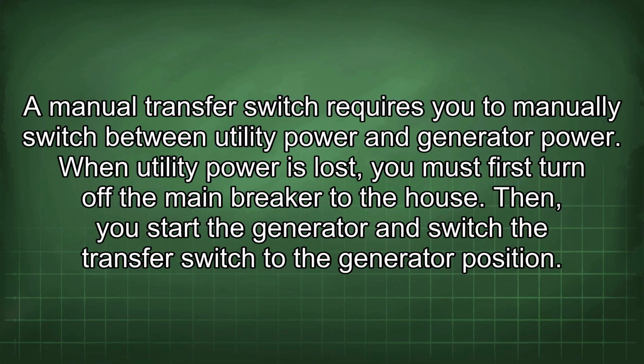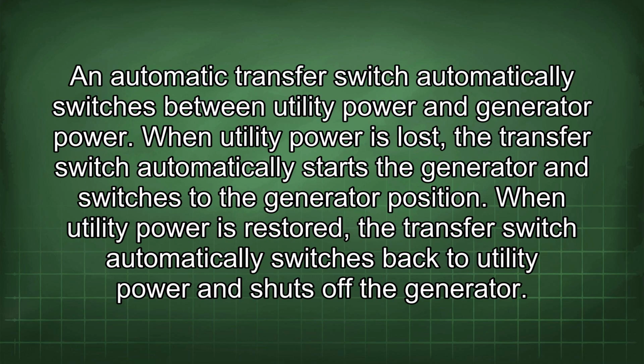A manual transfer switch requires you to manually switch between utility power and generator power. When utility power is lost, you must first turn off the main breaker to the house. Then, you start the generator and switch the transfer switch to the generator position. An automatic transfer switch automatically switches between utility power and generator power. When utility power is lost, the transfer switch automatically starts the generator and switches to the generator position. When utility power is restored, the transfer switch automatically switches back to utility power and shuts off the generator.